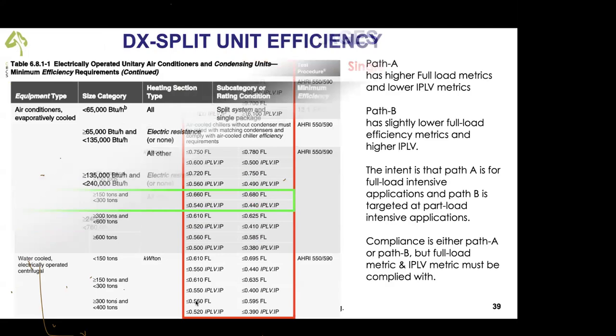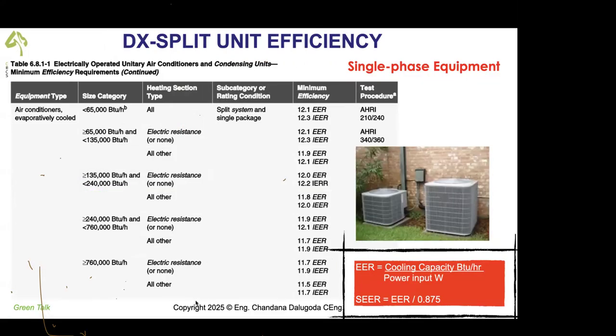Not only chillers, single phase equipment like split units is given as EER, energy efficiency ratio. Now, all of you listening, if you are buying a split type residential air conditioner for your office or your bedroom, don't stick to the price reduction. Don't stick to the name. Of course, you need the capacity, 12,000 BTU, 18,000 BTU, whatever. But the selection procedure is energy efficiency ratio, cooling capacity divided by power input, EER. Now, EER should be 12.